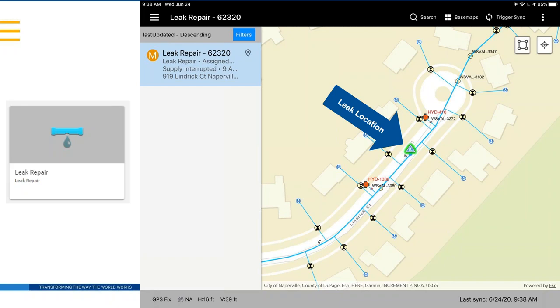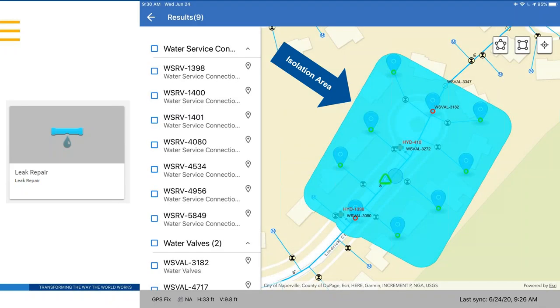Trimble Unity works with the geometric network for tracing. When a leak has been reported, an office or field user can create a leak repair job. In this example, somebody creates a job noting a leak at a specific location. A field person investigates — possibly visually confirming the leak, using our leak locator kit, or using electronic tools to pinpoint the exact location — and once confirmed, a repair needs to happen.